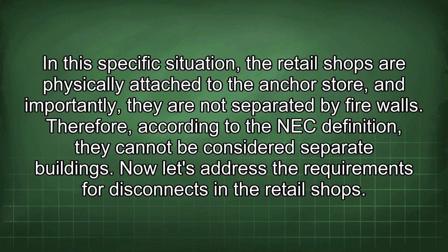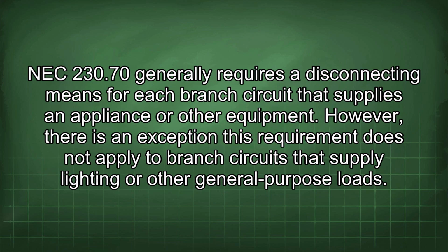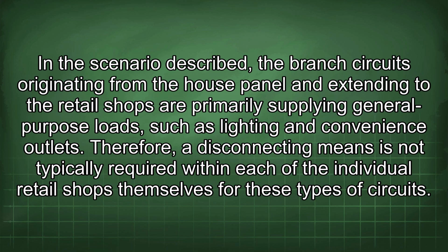Now let's address the requirements for disconnects in the retail shops. NEC 230.70 generally requires a disconnecting means for each branch circuit that supplies an appliance or other equipment. However, there is an exception. This requirement does not apply to branch circuits that supply lighting or other general purpose loads. In the scenario described, the branch circuits originating from the house panel and extending to the retail shops are primarily supplying general purpose loads such as lighting and convenience outlets.